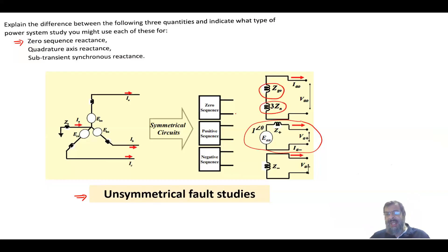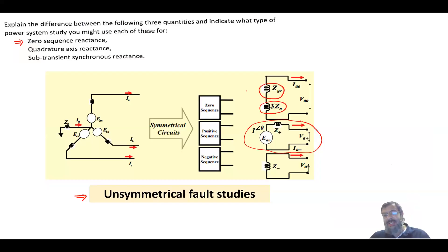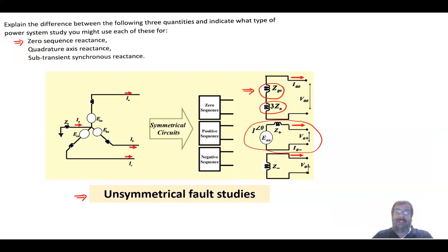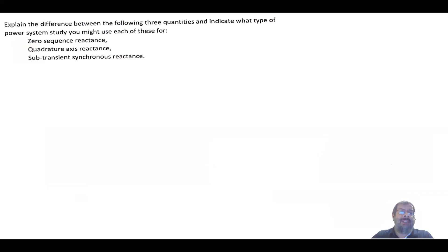The 3Zn term represents the reactance or impedance in the neutral multiplied by three, but that's not what the question was asking. The zero sequence reactance is specifically used in the modeling of the generator under unsymmetrical fault studies.